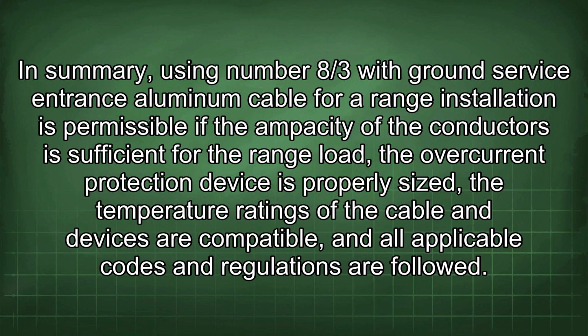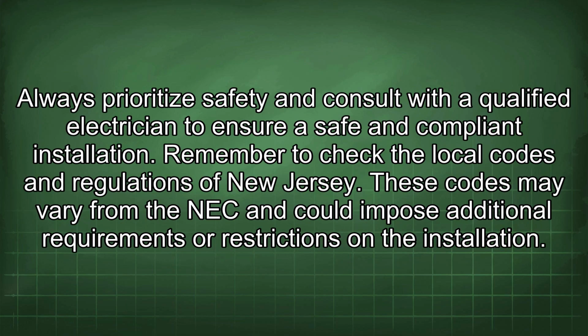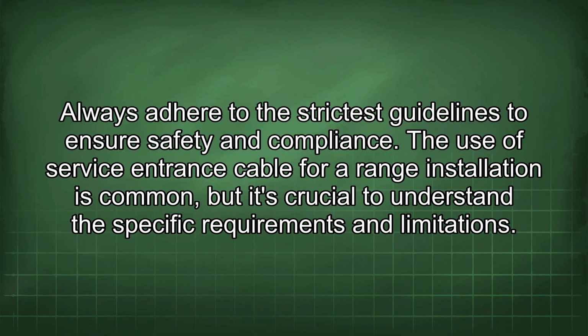In summary, using number 8/3 with ground service entrance aluminum cable for range installation is permissible if the ampacity of the conductors is sufficient for the range load, the overcurrent protection device is properly sized, the temperature ratings of the cable and devices are compatible, and all applicable codes and regulations are followed. Always prioritize safety and consult with a qualified electrician to ensure a safe and compliant installation. Remember to check the local codes and regulations of New Jersey. These codes may vary from the NEC and could impose additional requirements or restrictions on the installation. Always adhere to the strictest guidelines to ensure safety and compliance.